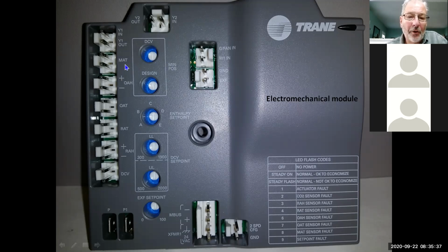The one thing you'll notice on here is we've got MAT, which is our mixed air temperature. Okay, that is the only input we really need. I mean, the outdoor sensor is part of the system, but we need the mixed air temperature. That's the one that goes on the blower housing. And that's what controls the modulation and the cooling call.